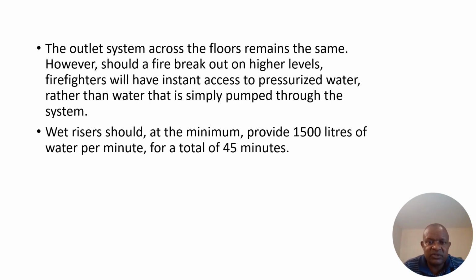However, should a fire break out on a higher level, firefighters will have instant access to pressurized water rather than water that is simply pumped through the systems. Wet risers should, at the minimum, provide 1,500 liters of water per minute for a total of 45 minutes.